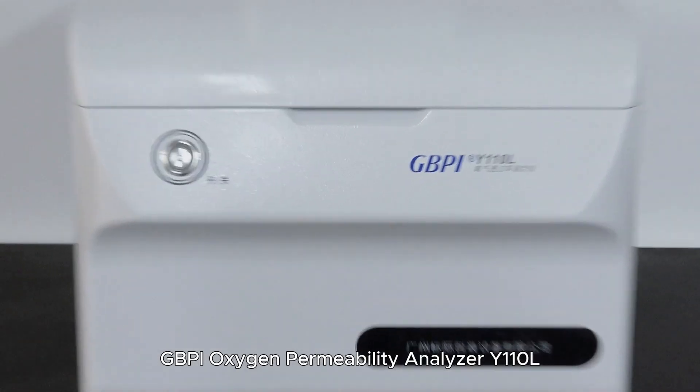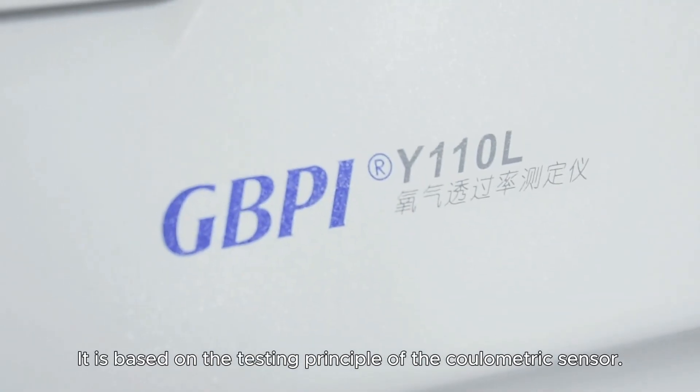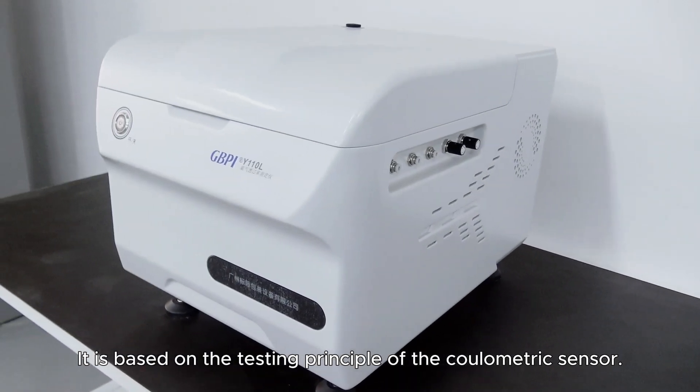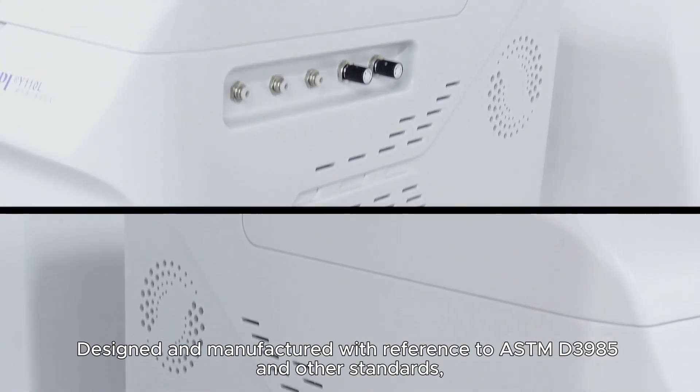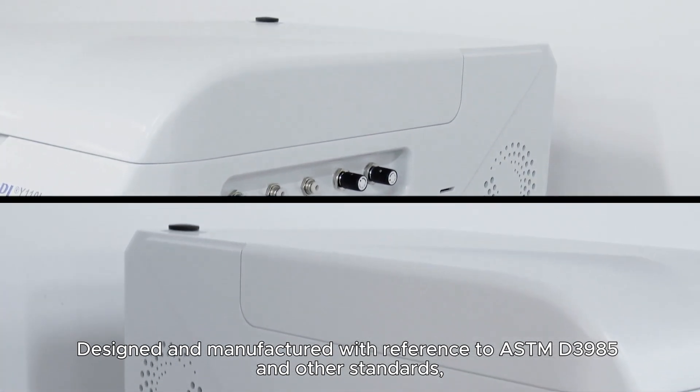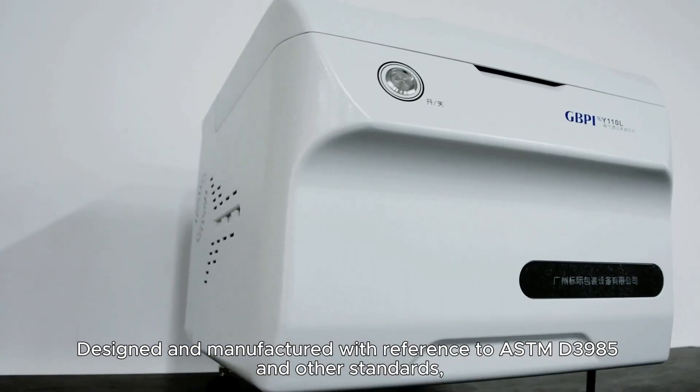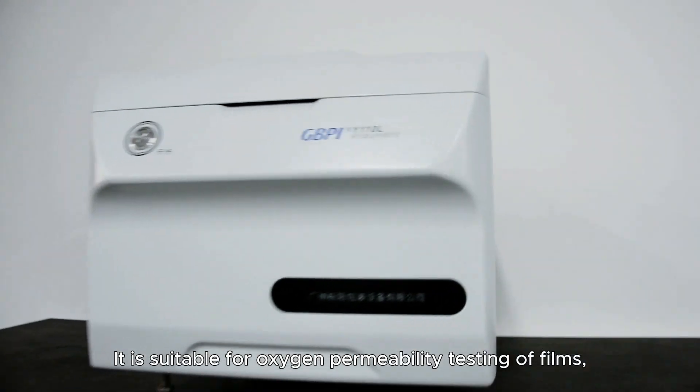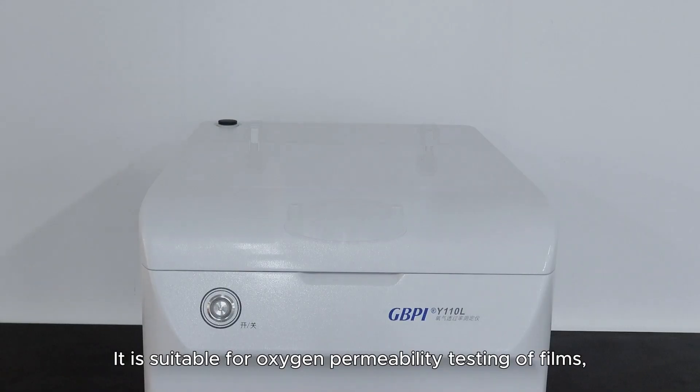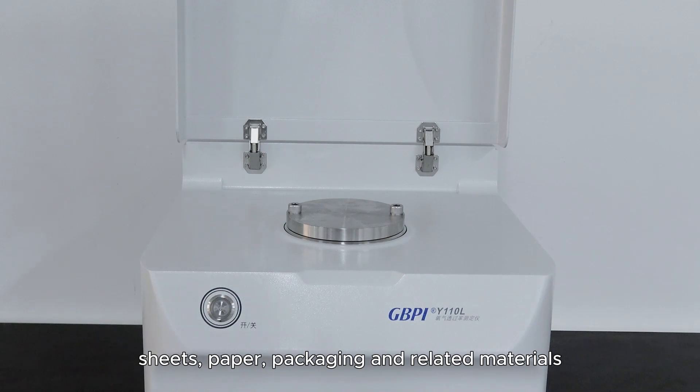GBPI Oxygen Permeability Analyzer Y110L. It is based on the testing principle of the coulometric sensor, designed and manufactured with reference to ASTM D3985 and other standards. It is suitable for oxygen permeability testing of films, sheets, paper, packaging, and related materials.